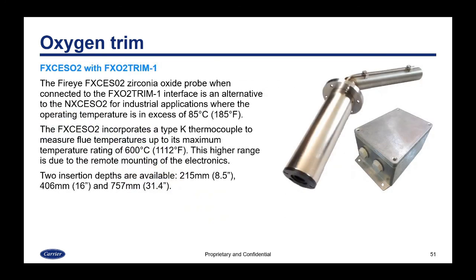If the ambient temperature range needs to be exceeded, we have another option, and that's the FXCESO2 with the FXO2TRIM-1 control board. And this is a zirconia oxide probe that is an alternative for industrial applications where the operating temperature would be in excess of 185 degrees Fahrenheit. This also incorporates a Type K thermocouple to measure flue temperature up to the maximum temperature rating of 1,112 degrees Fahrenheit. The higher range is due to the remote mounting of the electronics.